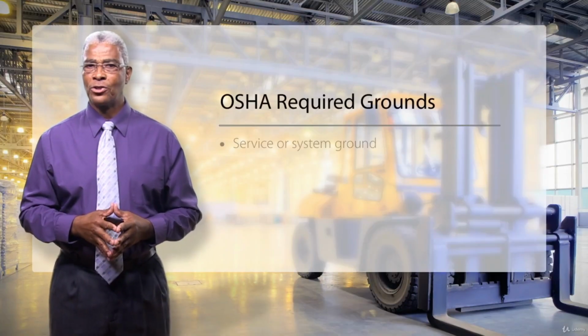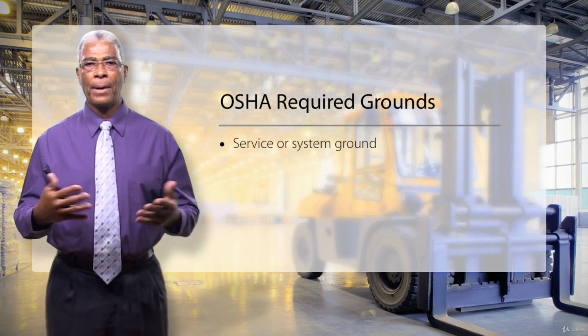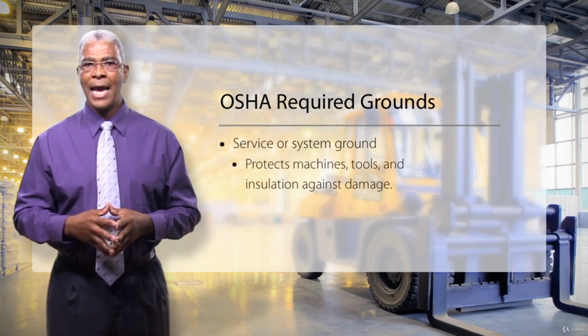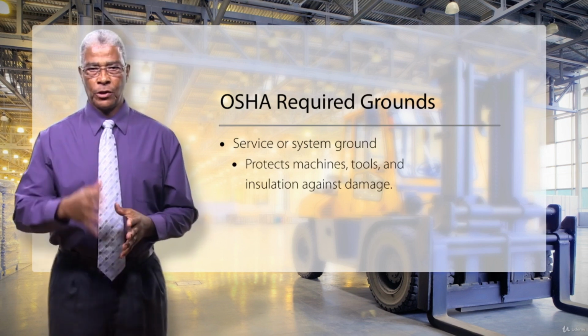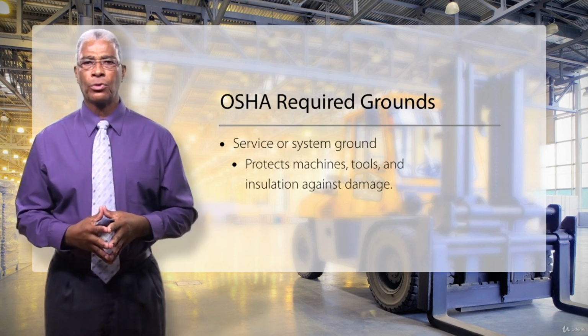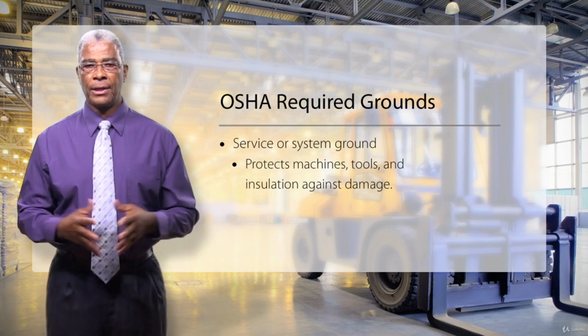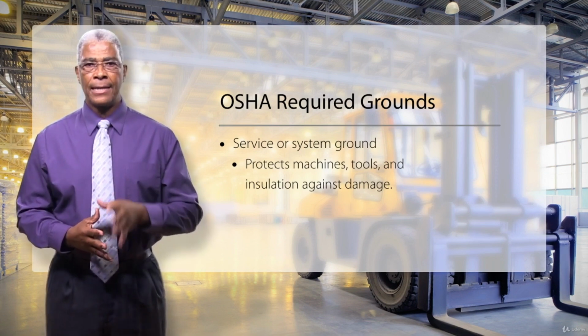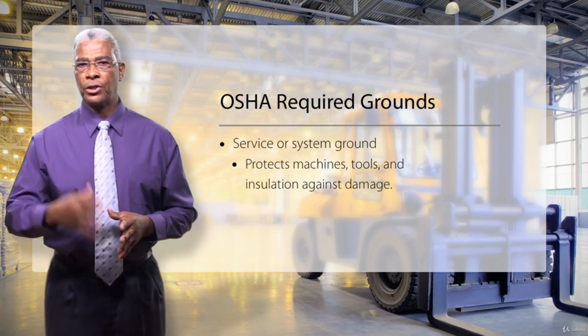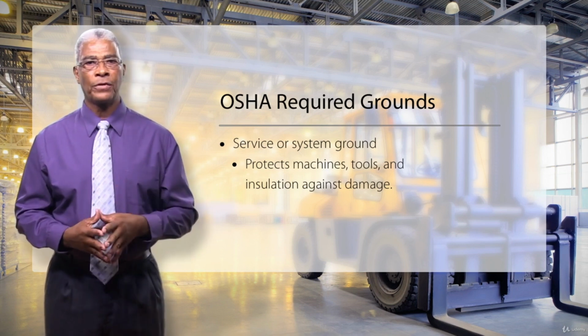First, there must be a service or system ground. This type of ground is primarily designed to protect machines, tools, and insulation against damage. In a service or system ground, one wire, called the neutral conductor or grounded conductor, is grounded. In an ordinary low-voltage circuit, this is a white or gray wire that is grounded at the generator or transformer and again at the service entrance of a building.